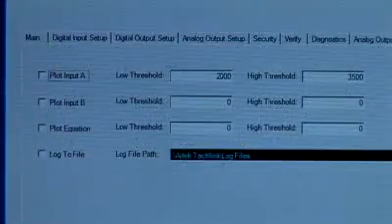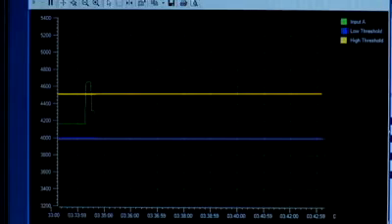Each source has a user configurable low and high threshold. These thresholds can be the same as applied to one of the outputs or other significant values. Each input source also has a span number associated with it. Span is a running calculation when plotting is active of the difference between the maximum and minimum values for each input source. The result is SPC type information about the process being monitored.